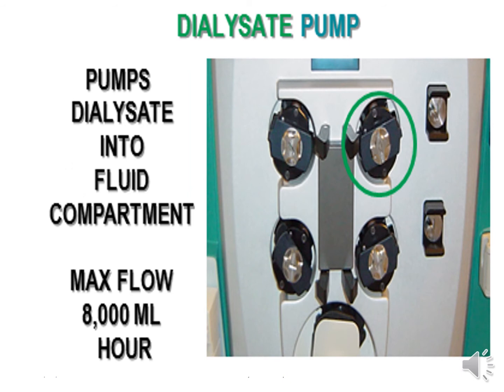You've got the dialysate pump, and this pumps dialysate into the fluid compartment at a flow rate of about 8,000 mils per hour maximum. Depends on how quickly you want to remove the product. So for example, if you've got a patient who's got hyperkalemia and you want to remove the potassium really quickly, you would have a high flow rate. If you've got urea, you may not want to remove it as quickly, because removing it too quickly may cause cerebral edema as a consequence.